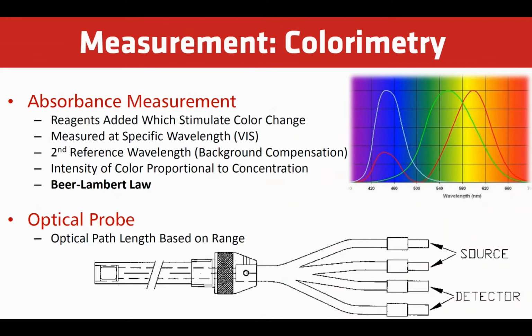We also use a second reference that does not see the color, but it accounts for turbidity in the sample or some air bubbles or lamp aging. So now it's just standard Beer's law at this point. It gives us the absorption value at the wavelength of interest, corrected for lamp aging or particulates in the sample or air bubbles in the sample on the optical path.